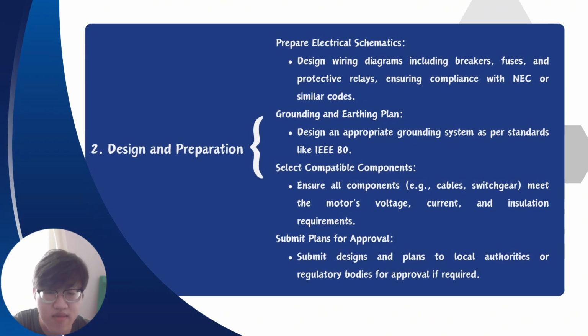Secondly, design and preparation. First, prepare electrical schematics like a wiring diagram, including breakers, fuses, and voltage relays, ensuring compliance with NEC or similar codes. This can help the engineer to have easier wiring, thus a grounding and earthing plan. Design an appropriate grounding system as per standards like IEEE 80.